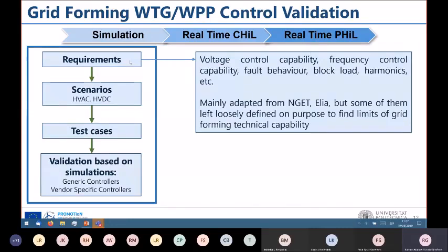So we started with requirements. These functional requirements were slightly different than normal grid code requirements, as we are talking about a different operating mode of the whole wind farm, mainly voltage control and frequency control. Now it has to be done directly by the wind farm, and those are mainly adapted from NG ESO and ELIA codes for black start requirements. Then we have studied the three scenarios that we were talking about before, HVAC and HVDC, and we have been carrying out a lot of test cases on those scenarios just to be able to show that these controllers comply with the requirements. And finally, these simulations have been done both with the generic controllers and also with black box controls from vendors.